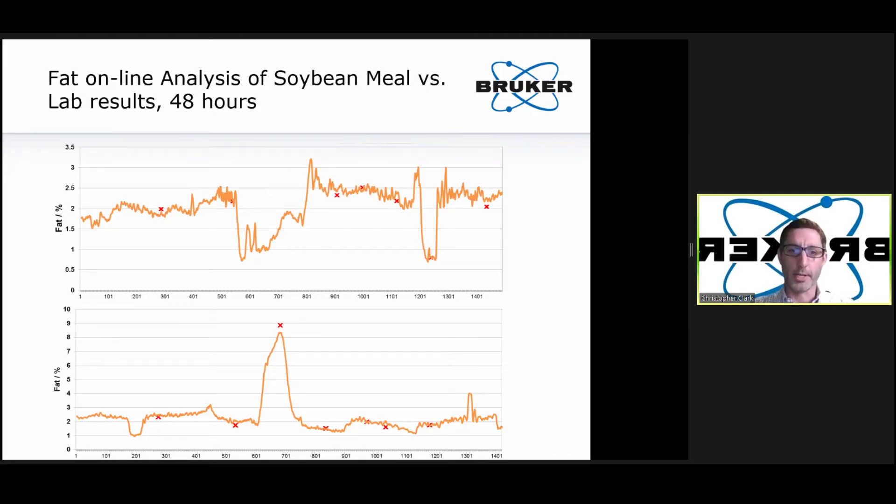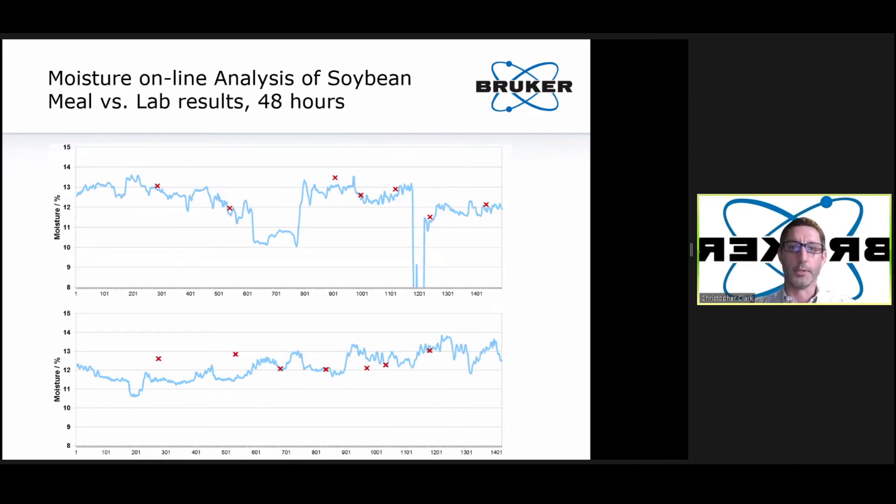And you can see, this is just an example of fat trending over time. The orange line represents the results from the spectrometer, and the red X's represents grab samples that were pulled and run to test against the results of the spectrometer. And you can see a pretty tight correlation with how the analyzer is actually reading versus what the lab results are showing. So this is conceptual proof that you can use this technology to accurately monitor your process in more real-time fashion.